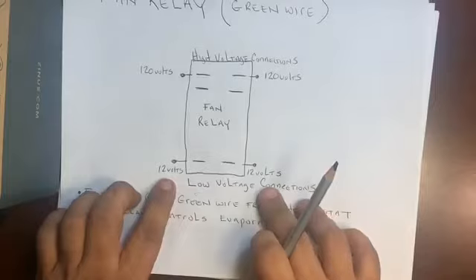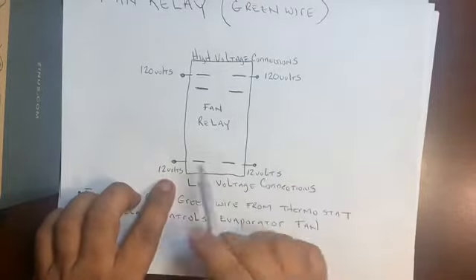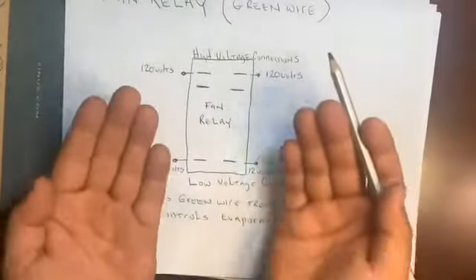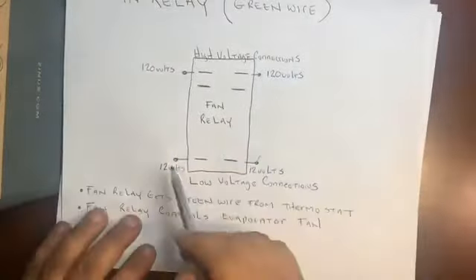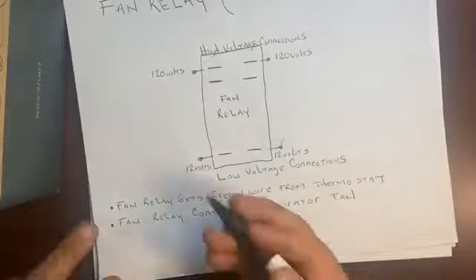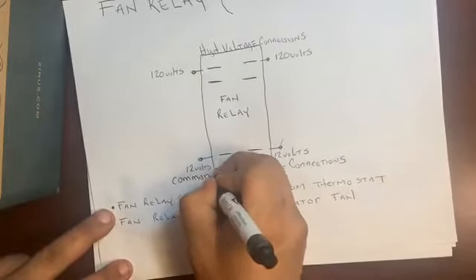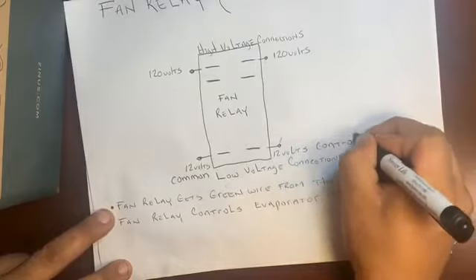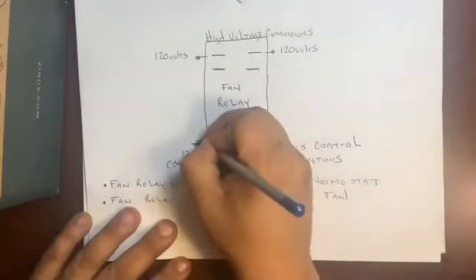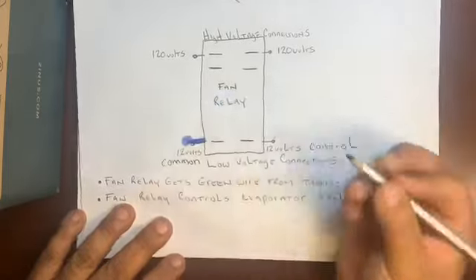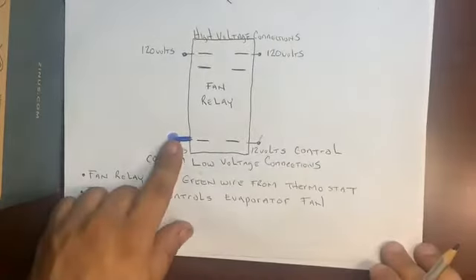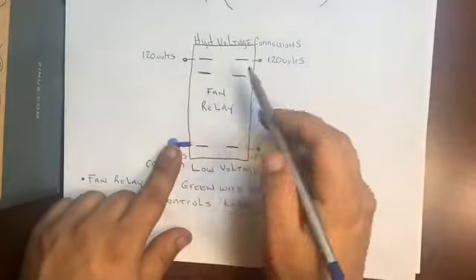So low voltage connections, a relay has a low voltage connection. It has 2, 12 volts on one hand, 12 volts in the other hand. Try to think of your low voltage connections as 2 hands. You have 2 hands. Every relay has 2 hands of low voltage. 2 hands, not 1 or 2 or 3, but 2. Okay, so with this, what are we gonna do? We're gonna designate a 12 volt common. And of course a control. What color is common? All day with us, it's blue. So now this fan relay is ready to accept 12 volts common and 12 volts control to turn on this connection and to bridge this gap and send 120 volts to turn on the fan. This is our fan relay.